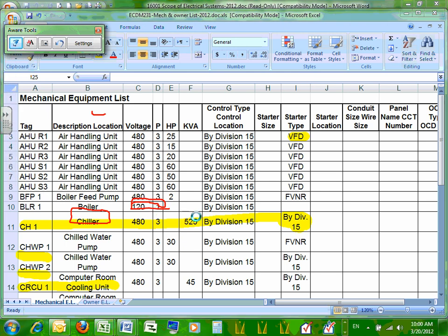Well, yeah. So what it's saying, in simple terms, is the largest motor. I'm okay moving it to a motor, but in the big scheme of things, and I'm sure Guy would agree with me, 25% of the largest motor on a project like this, which is 4,000 amp, doesn't make a whole lot of change in the big scheme of things. Well, since we're organizing and categorizing things, I think that's a valid point.